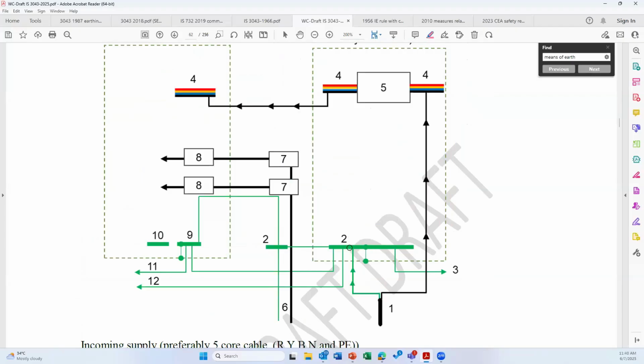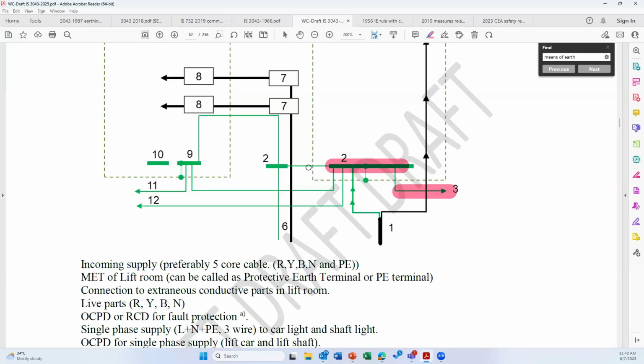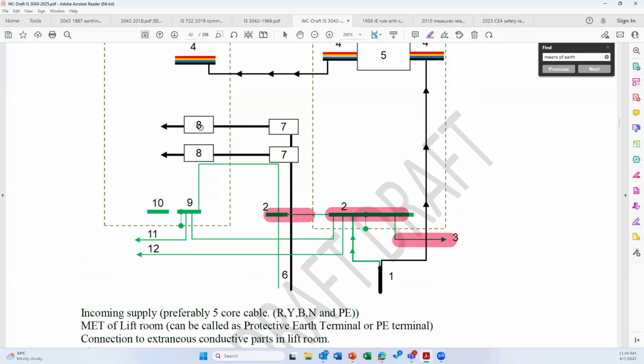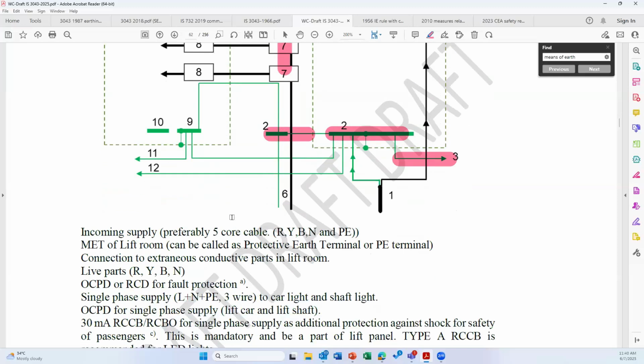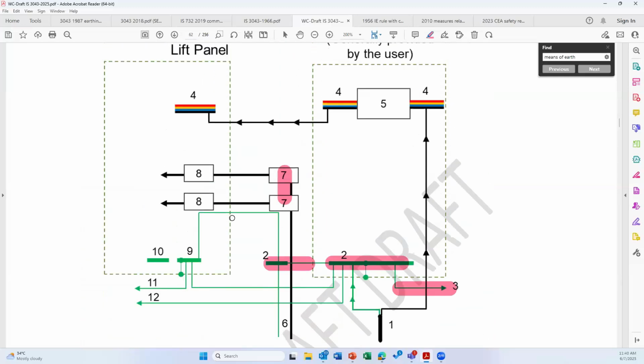Now, from this serial number 2, it goes to, for example, the rail or the live parts. Then it goes to the car. Then it goes to, for example, number 7, number 8. These are the protective devices such as a 30 milliampere RCD, because the idea is, the lift, as per IS 17900, needs protective earthing. Fault protection is achieved by protective equipotential bonding and automatic disconnection of supply.